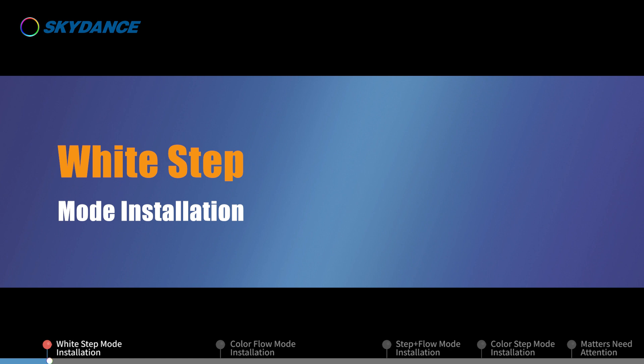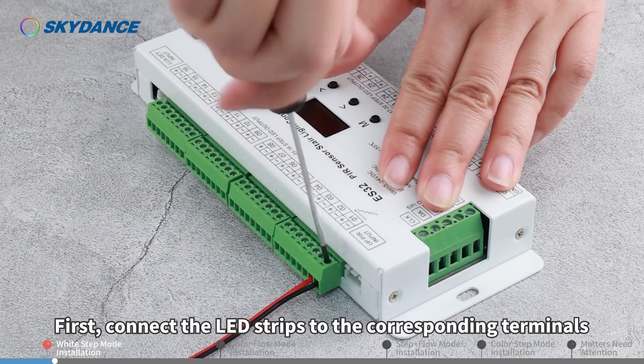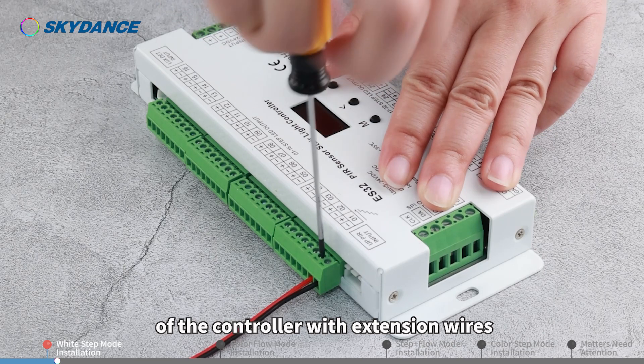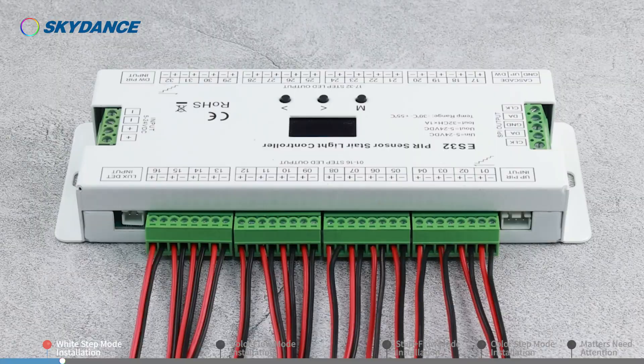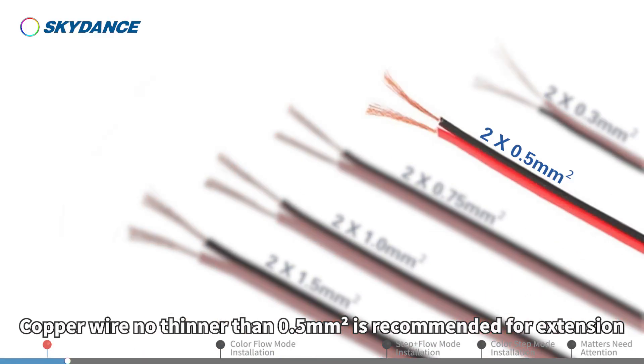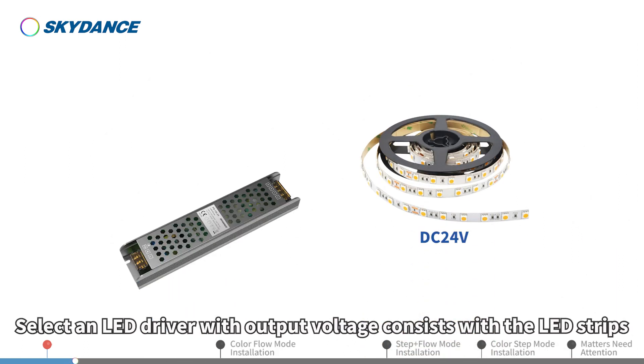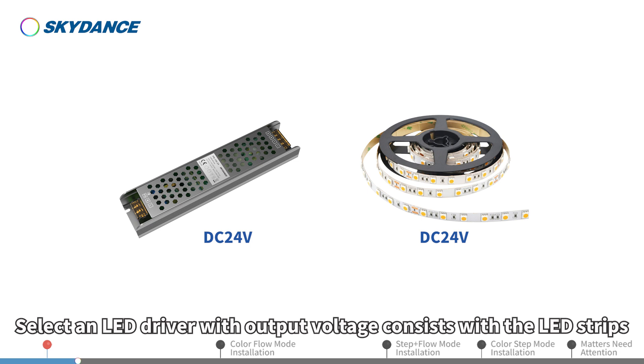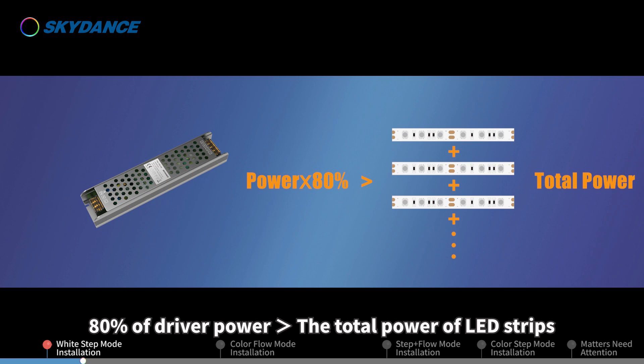White Step Mode Installation. First, connect the LED strips to the corresponding terminals of the controller with extension wires. The first step connects to terminal 01, and so on. Copper wire no thinner than 0.5 mm² is recommended for extension, and the length should not exceed 10 meters. Select an LED driver with output voltage consistent with the LED strips, with 80% of driver power greater than the total power of LED strips.